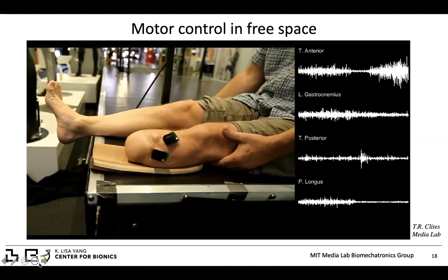Okay, sure. So I'm going to go to the next slide because I was up to it anyway. We designed, or actually Sung Ho Yang and his sub-team designed, what's called a slip electrode, like a slip that you wear and it slips under the silicone prosthetic liner. The electrodes are in between the socket and the residual limb, which is what we call the rest of the limb that's left after the amputation.